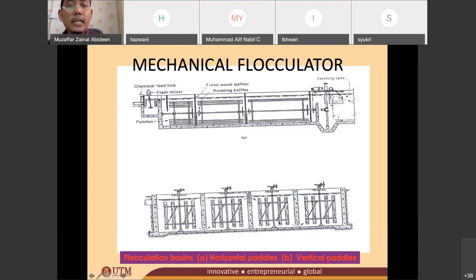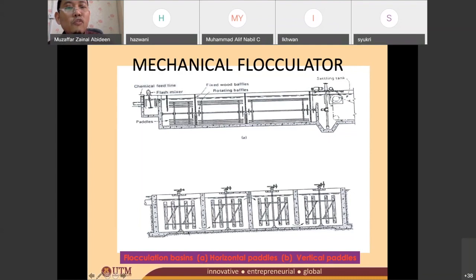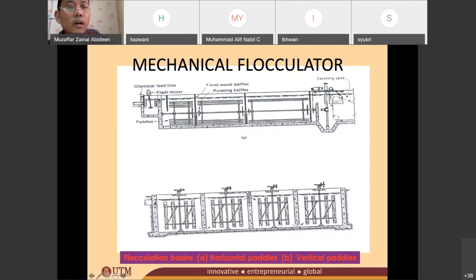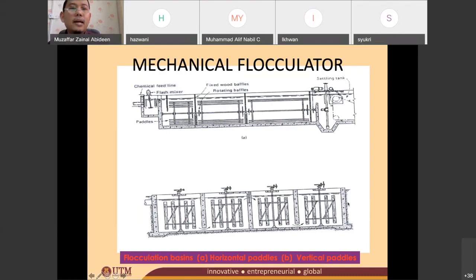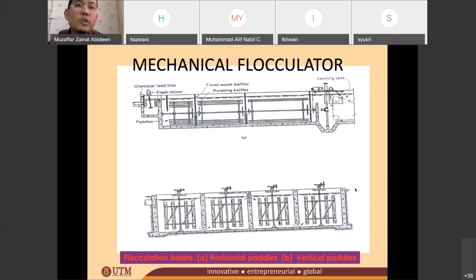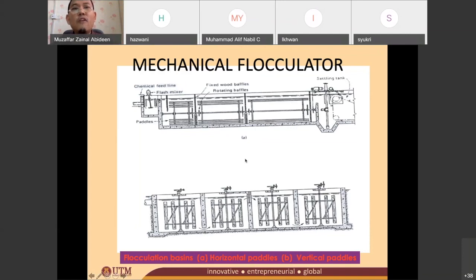This is one type of mechanical flocculator, and in this design they purposely put a barrier here — an obstacle. Why? It is to force the water to travel from one paddle to another paddle. Without these obstacles, the water can straight away go from one end to the other — this is called short-circuiting, where the water bypasses the paddles. If short-circuiting happens, the retention time t is very small and you may not be able to produce a good Camp number.